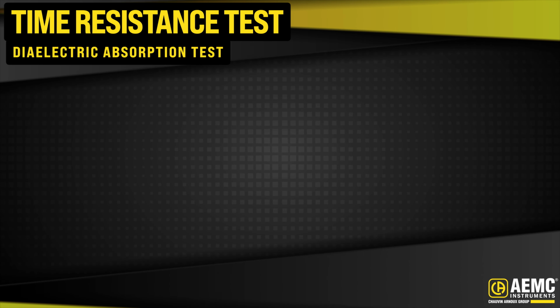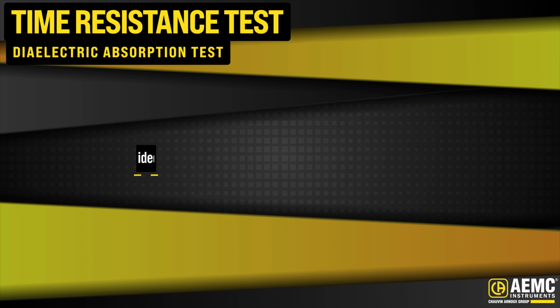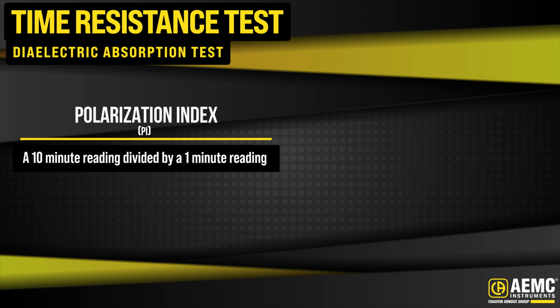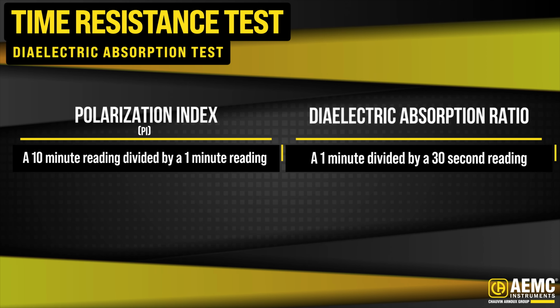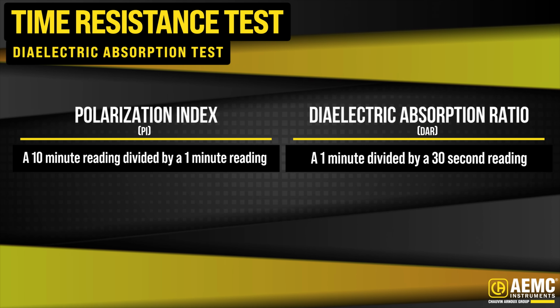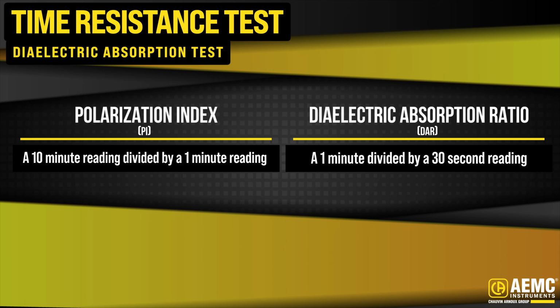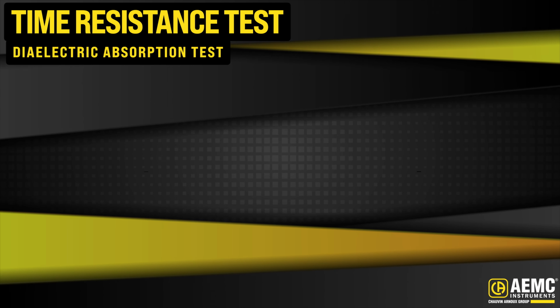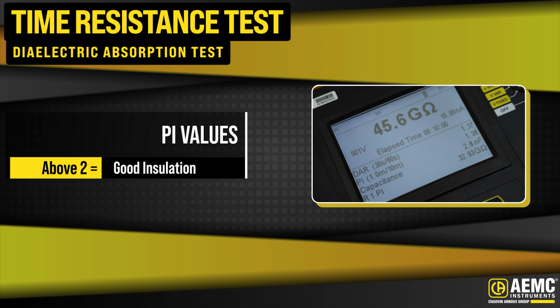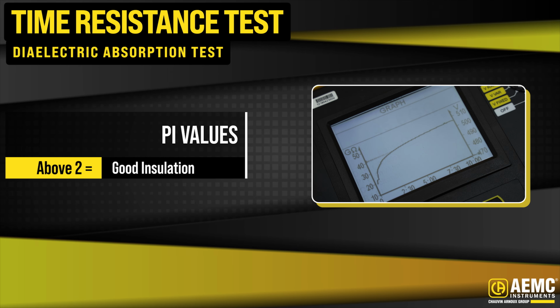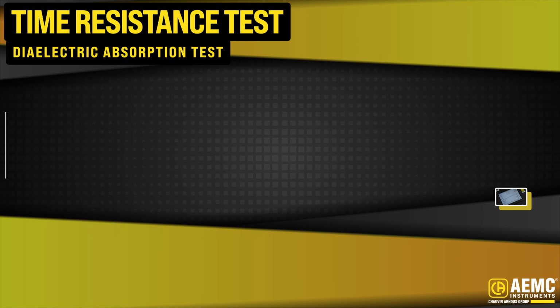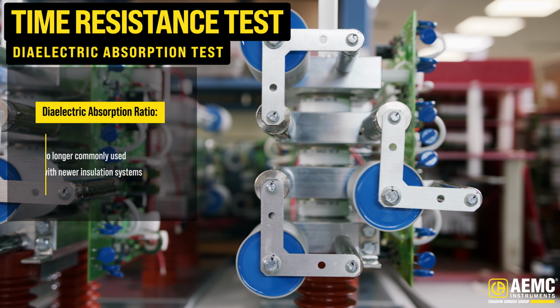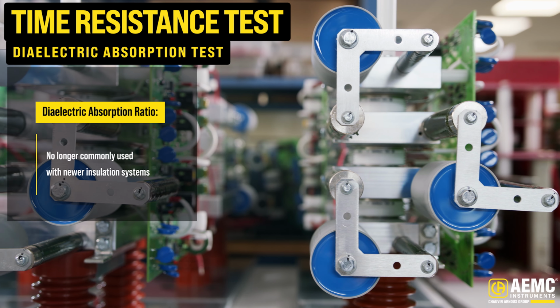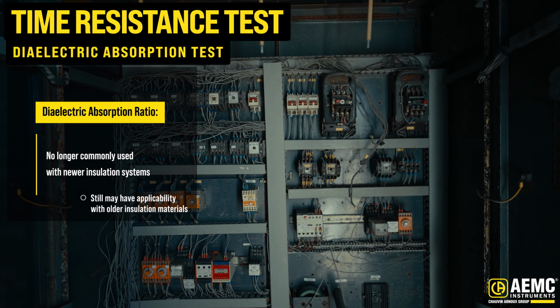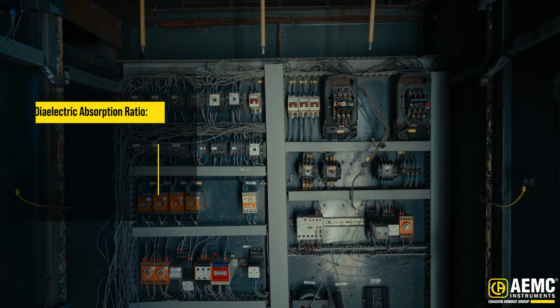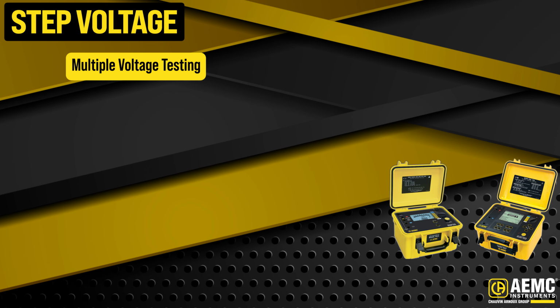From this data, two ratios can be calculated: polarization index, or PI, a 10-minute reading divided by a 1-minute reading, and dielectric absorption ratio, or DAR, a 1-minute reading divided by a 30-second reading. PI values above 2 usually indicate good insulation. Lower values may mean moisture or contamination. Although DAR is no longer commonly used with newer insulation systems, it still may have applicability when testing older insulation materials. A third method is the step voltage test.